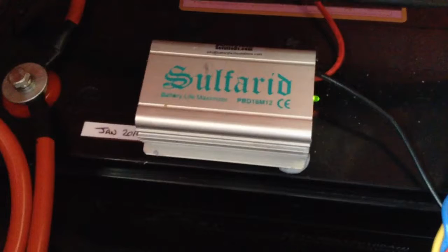Also, we have a battery desulfator. It just keeps your batteries healthy by stopping them from sulfating up. Your batteries sulfate up mainly if you draw them down to a low voltage, use your stuff a lot, and then don't charge them back up. So if you used a lot of load, used your inverter a lot, and say the weather was miserable and dark so you didn't get much solar, if your batteries stayed discharged for long periods, they sulfate up, and that's very bad for your batteries. It means they'll get hard to charge and their capacity will decrease, and if you do it too long, you'll be looking at a new set of expensive batteries.